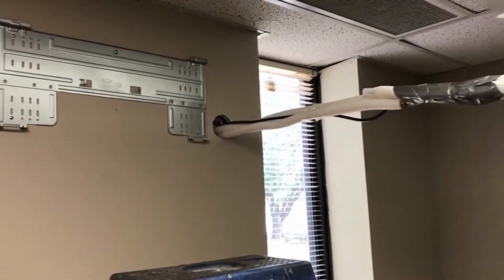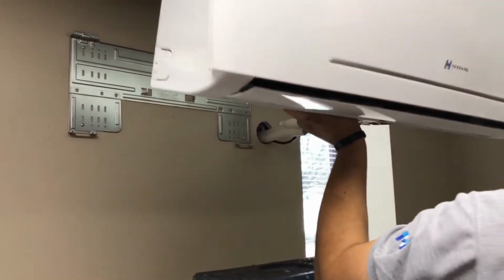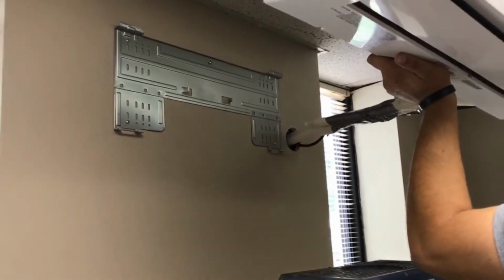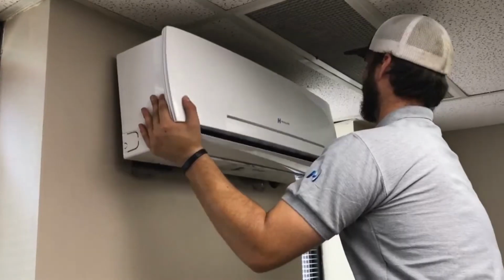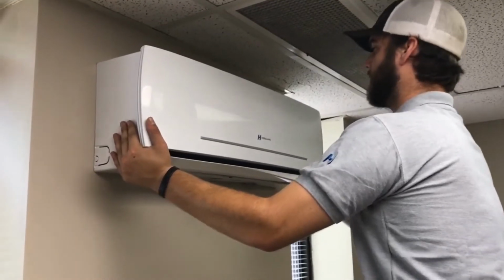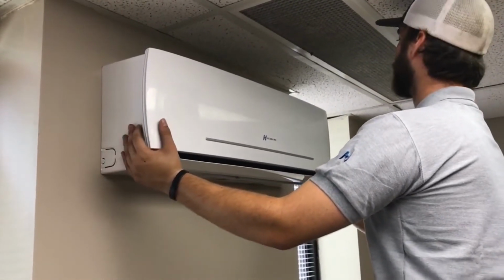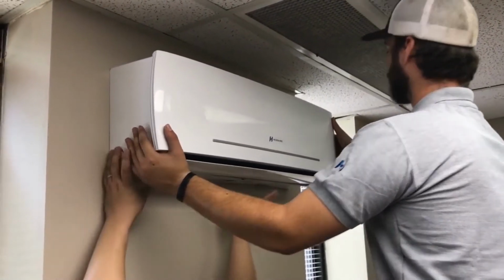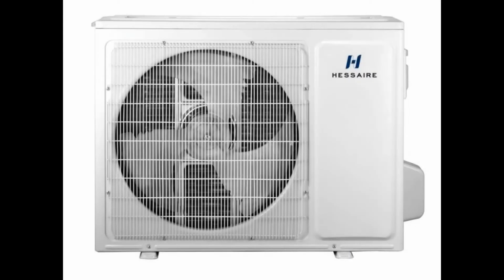Lift the unit into place and carefully pass the bundled pipes and wires through the wall opening. Place the air handler on the wall mount, making sure it is firmly secured and your refrigerant line, condensate tube, and electrical cables are completely through the wall. You're now ready to install the outdoor heat pump condenser.